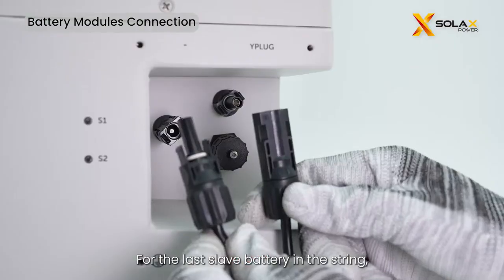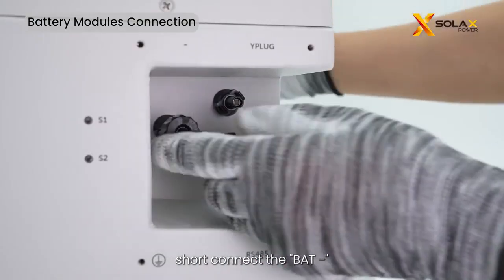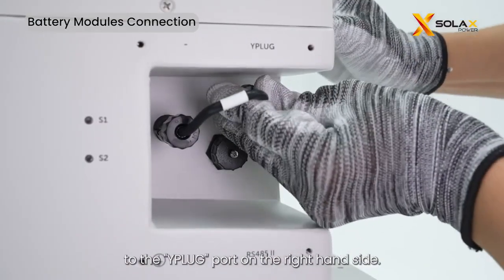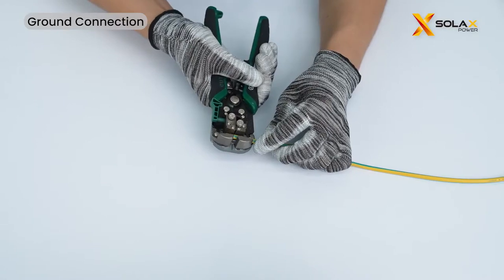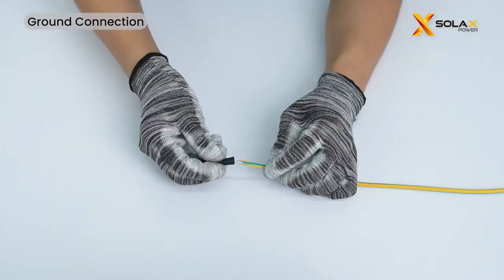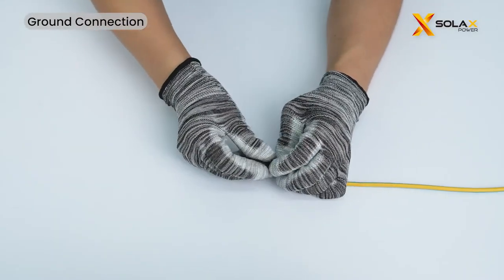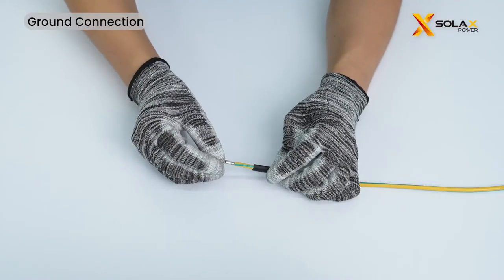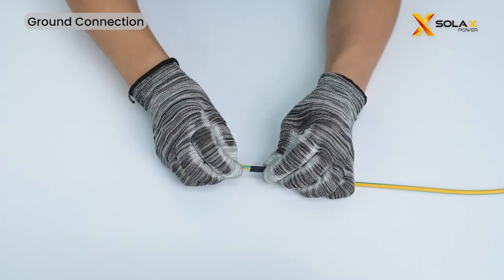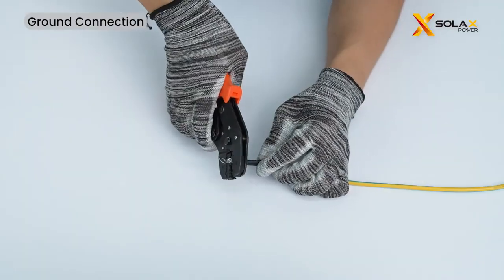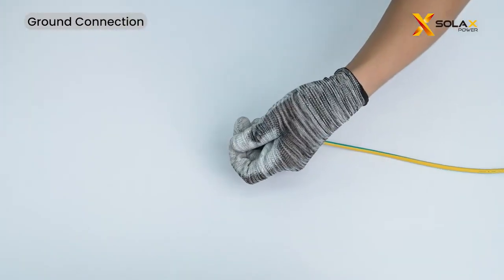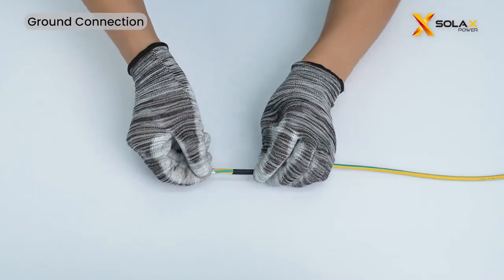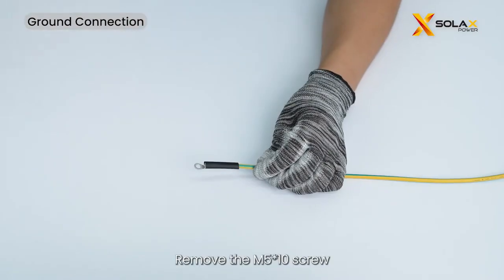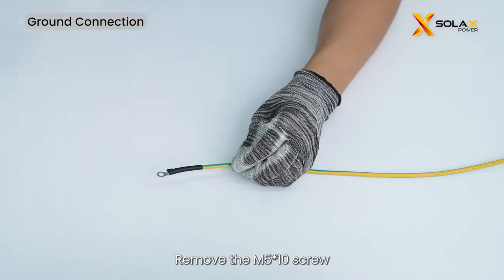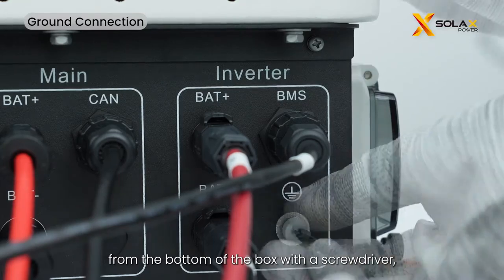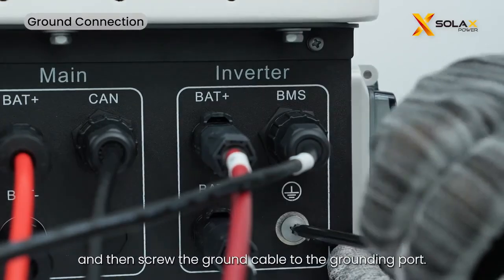For the last slave battery in the string, short connect the BAT negative to the Y-PLUG port on the right-hand side. Remove the M5*10 screw from the bottom of the box with a screwdriver, and then screw the ground cable to the grounding port.